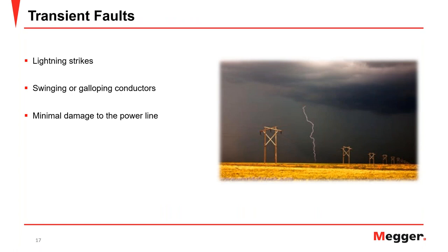Transient faults are most commonly caused by lightning strikes and swinging conductors. These faults tend to last only milliseconds or a few cycles of the system. They cause minimal damage to the power line and tend to clear themselves. Protection functions can still pick up these faults, sometimes open the line, and then restore power automatically.